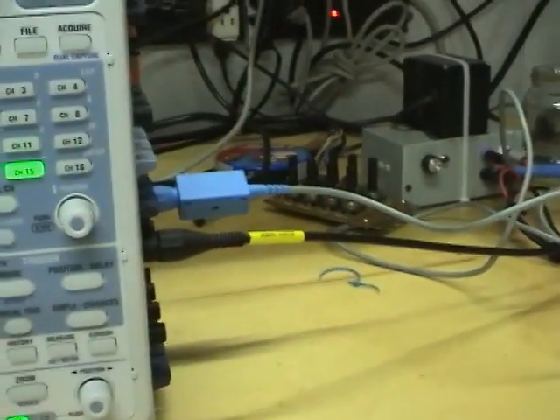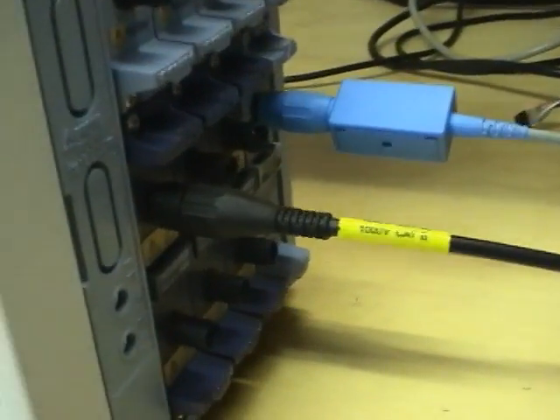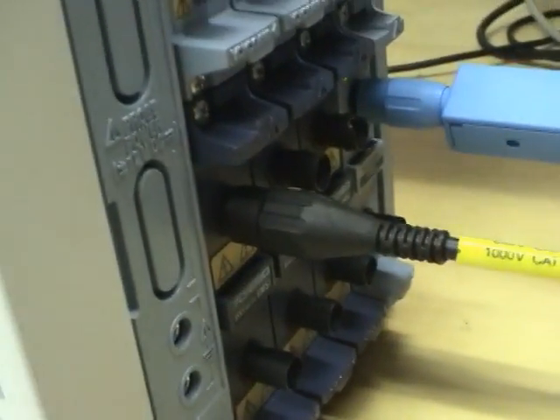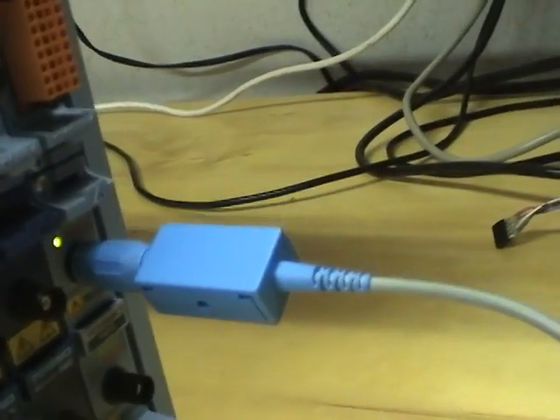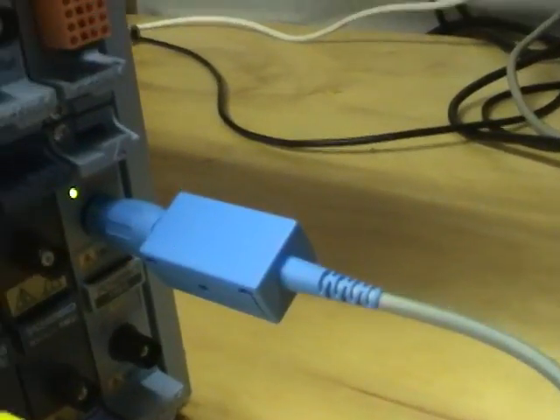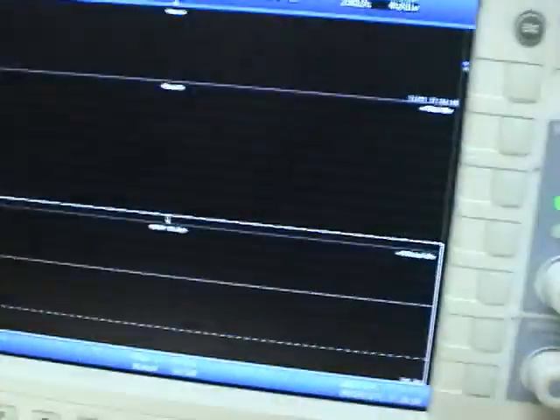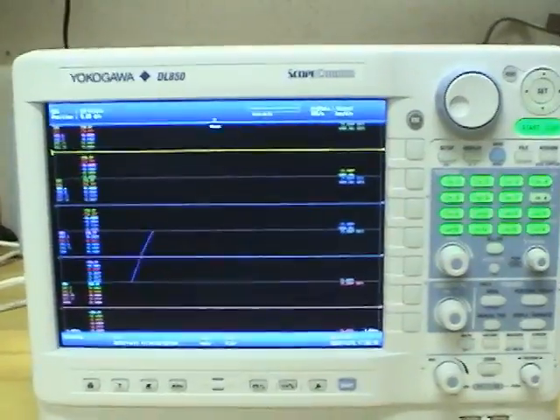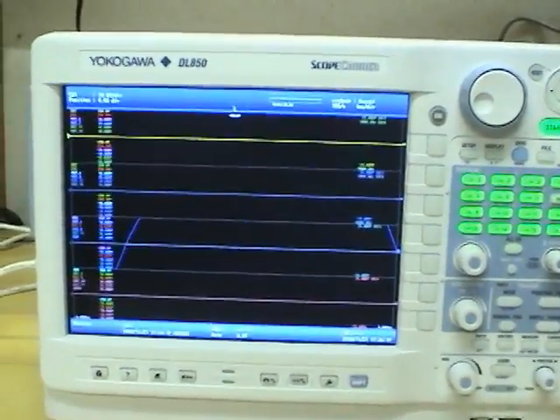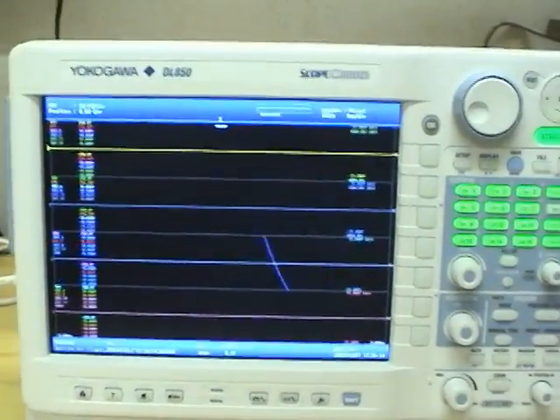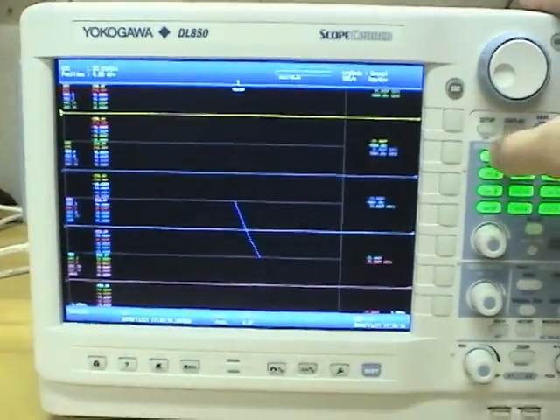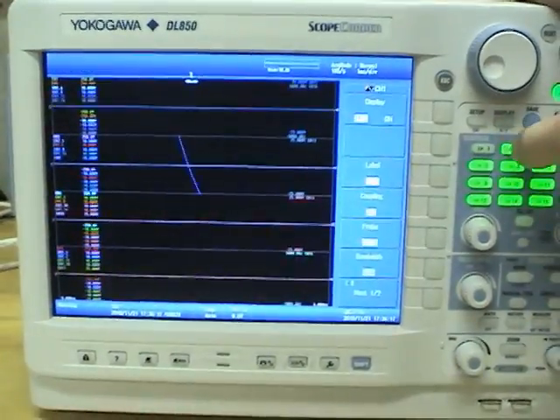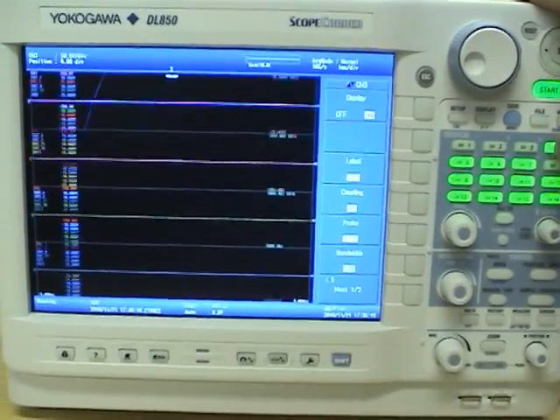Now let's see if we can make it display something. I've just got it connected right now to line voltage on channel 9 and frequency is also connected to line frequency. Let's just try to get a measurement of that. After restoring it to the default setup all the channels are on so let's just start turning off the channels we don't need.